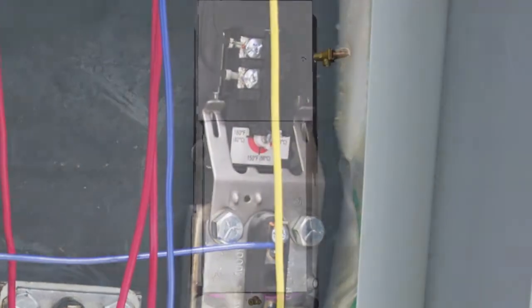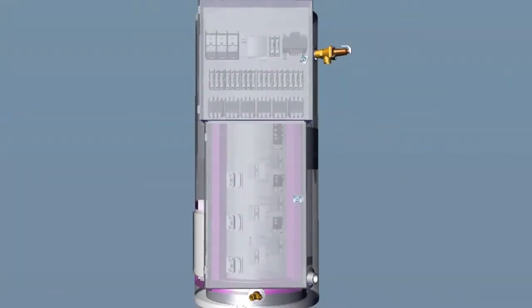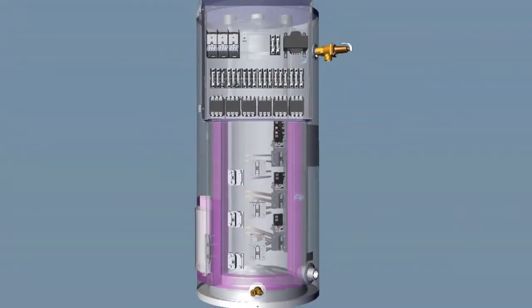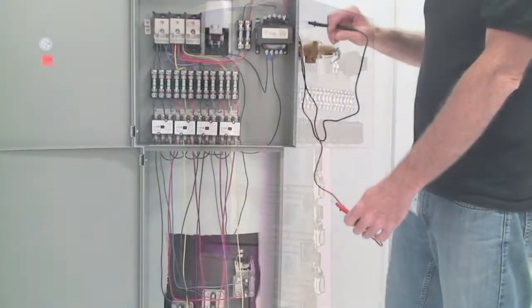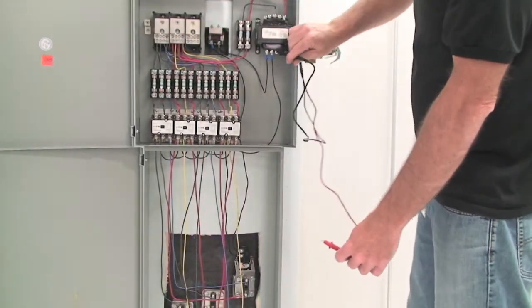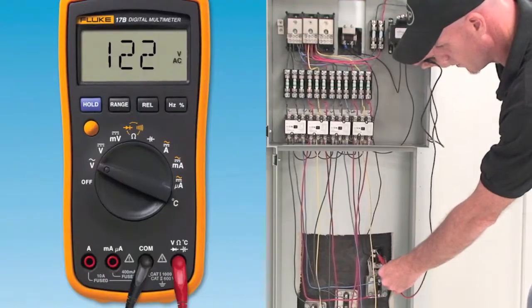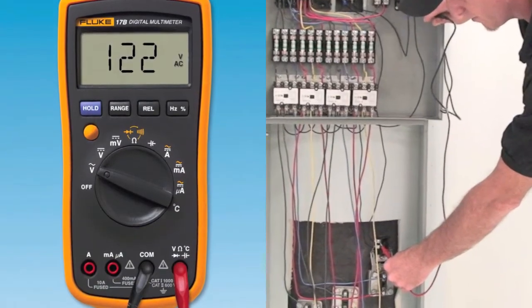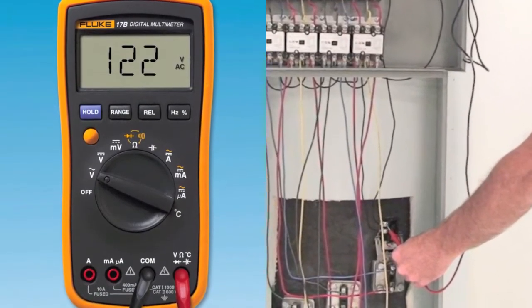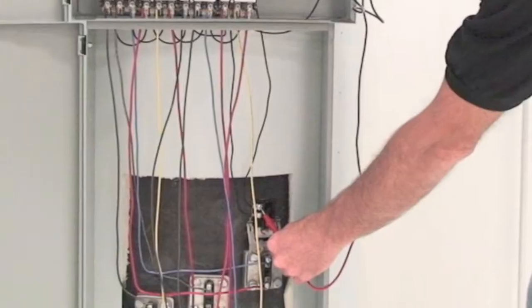To verify that the thermostat is either in the open or closed position, verify the thermostat setting is above actual water temperature. Measure supplied power of 120 volts AC using a multimeter with one lead on the upper terminal of the thermostat to the X2 designation on the transformer output side. This should read 120 volts AC.